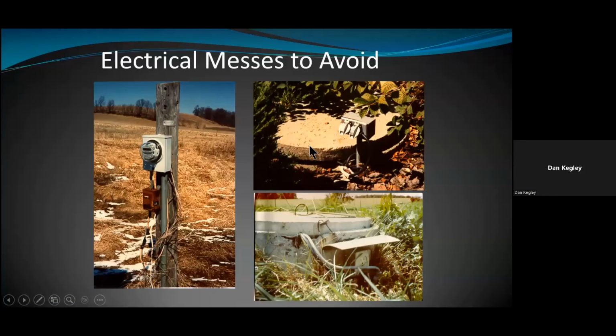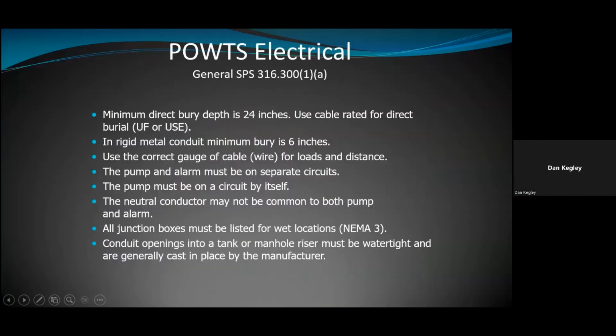Rigid metal conduit minimum burial is 6 inches. If you notice back in the chart, it didn't matter what type of product you were using. Even if you're using metal conduit, you'd still have to go down to the same burial depth. So if we go back to that chart, this is specific to direct burial. Then it says rigid metal conduit here in column 2, or intermediate metal conduit. So you have rigid metal or intermediate, IMC or RMC.